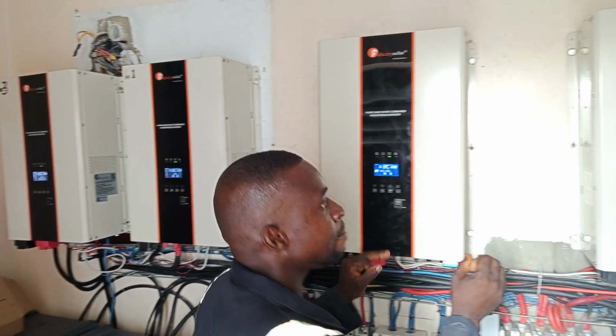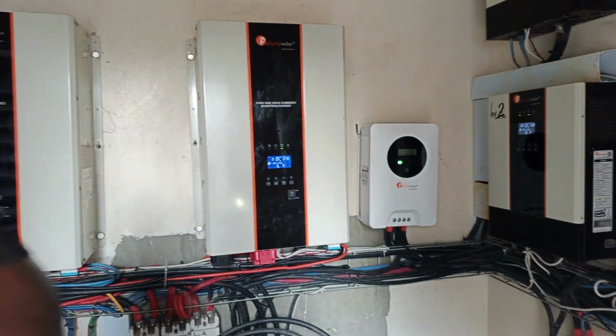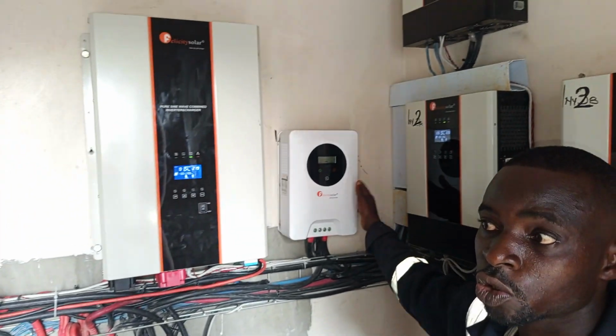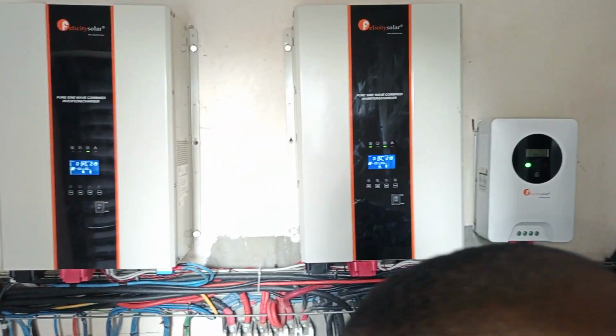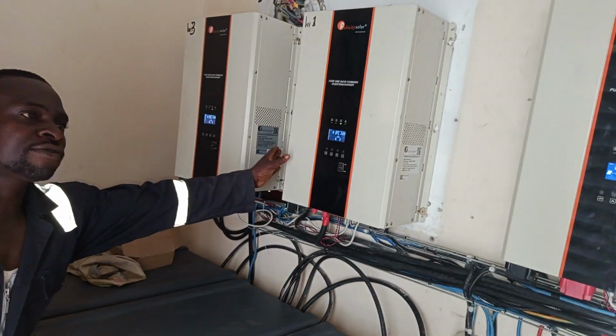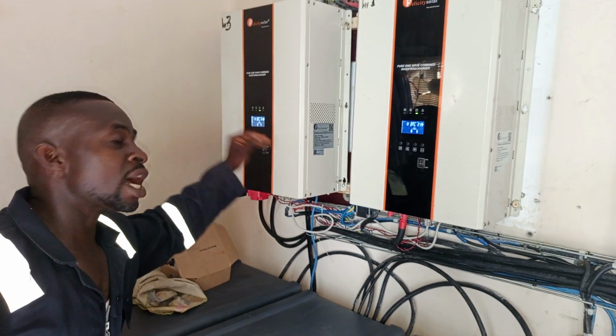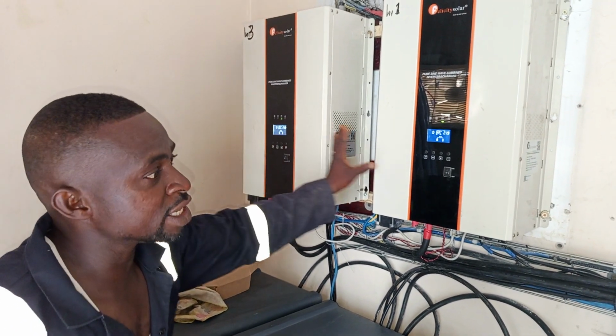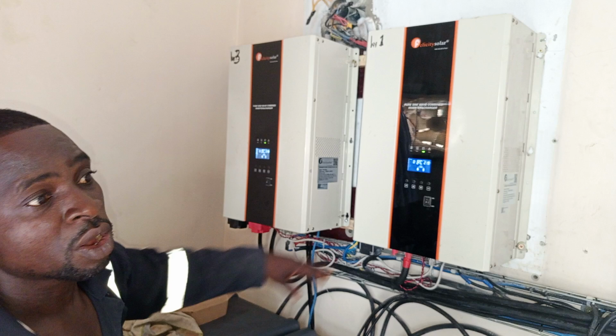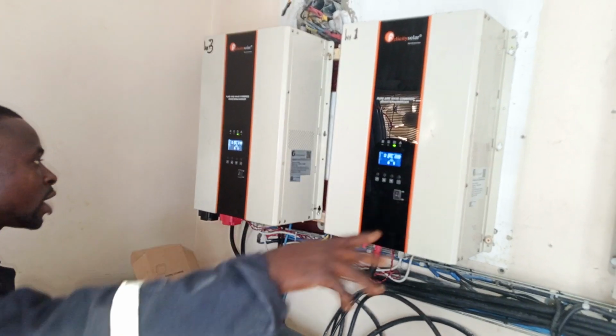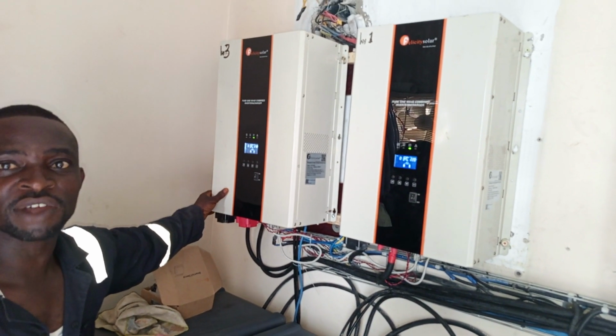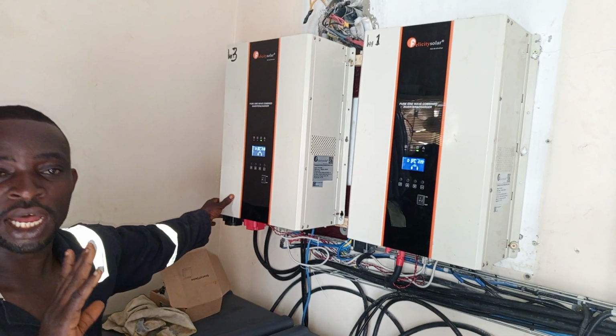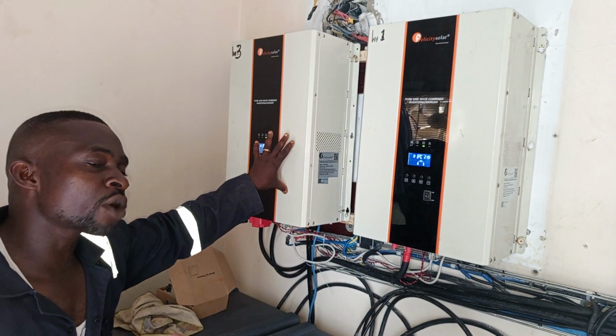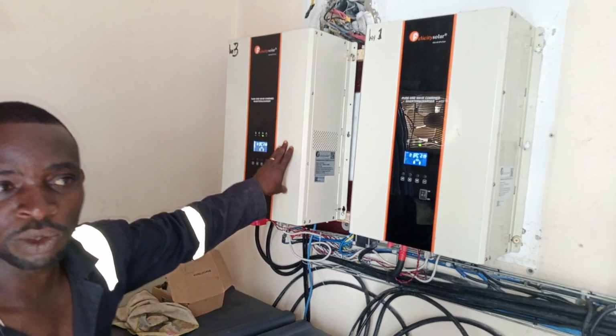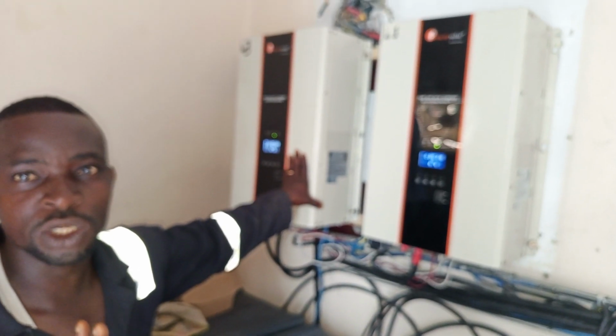Then we have one controller there, as you can see. This controller is also for this 10 kVA. As you can see, this is 10 kVA and this is 10 kVA. These 10 kVA units are not hybrid, they are non-hybrid. One of them is using that type of controller, but one of these inverters doesn't use any charge controller. Besides, we configure it for charging, because the reason for your design is that you have to calculate your charging current, what is going to charge your battery.